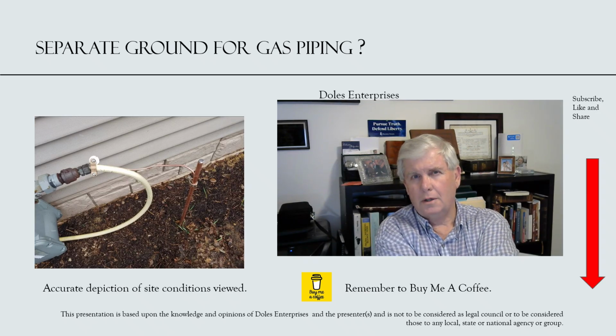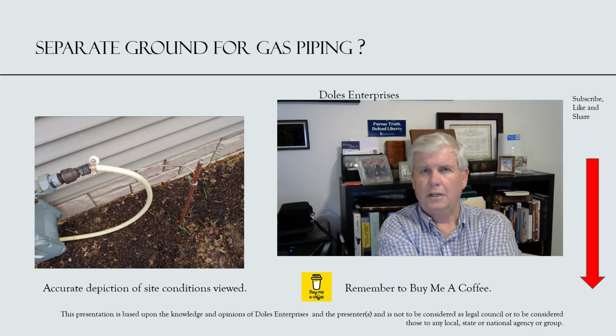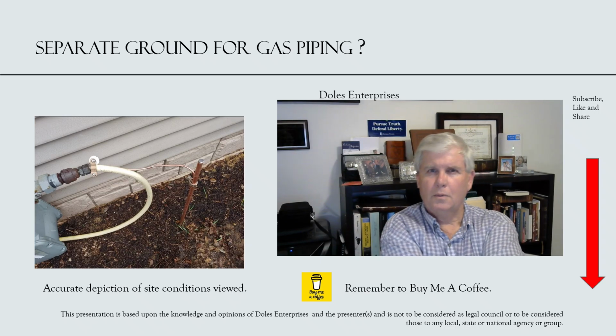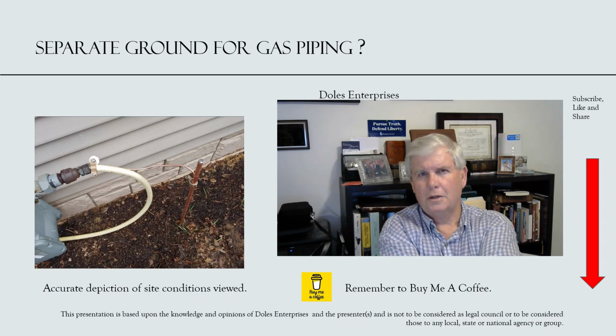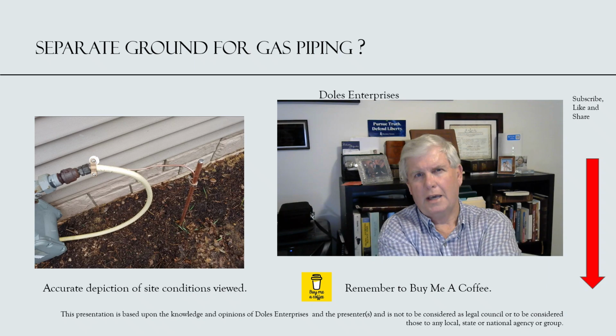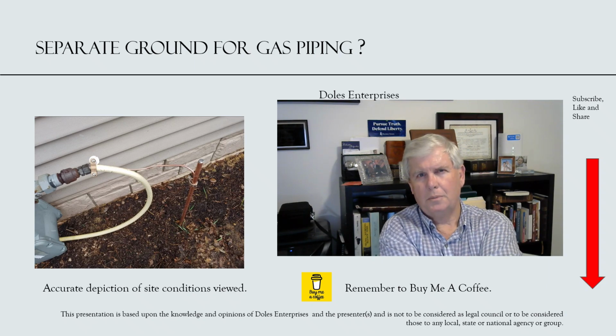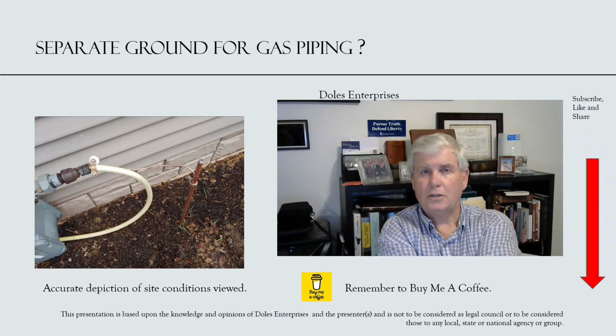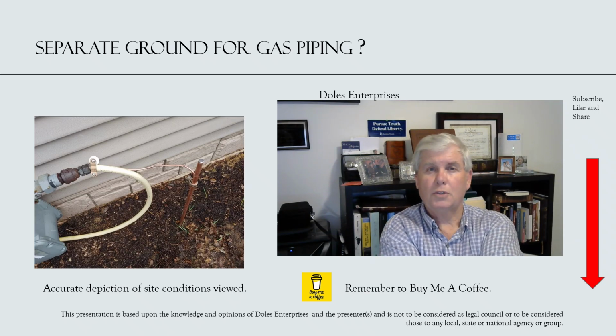Now, what you're seeing here is the contractor called me up all upset because he said the inspector wanted him to drive a ground rod and then run an equipment grounding conductor from the rod to the gas pipe. What had happened is he put in a new air handling unit in this house, and the inspector went in and asked about how it was bonded to the system, and the mechanical contractor was at a loss because he's not an electrician. So he did what the inspector told him to do, and he sent me a picture. It looked very similar to what I found right here that you're looking at.